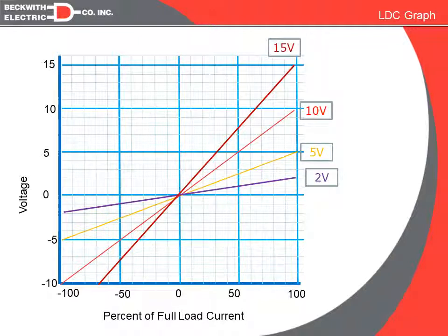But if we're in reverse power due to DG, for instance, distributed generation, in that case our source is still our source, and now we actually have current flowing from load to source instead of source to load, and that's when we would have to flip the sign. We're going to cover reverse power in a different session, and you can reference that session also.